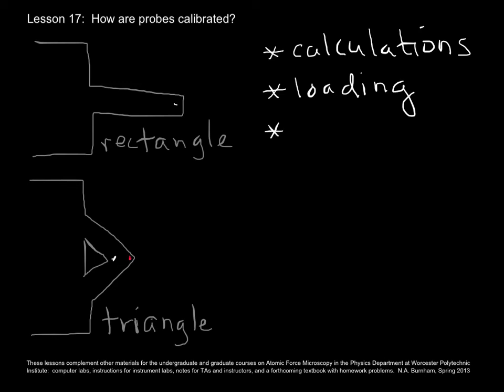There are a variety of options that I would call geometric, which is you measure the width and length of your cantilever, and that you can do optically because the lengths certainly are big enough and the widths are generally big enough that you can see that in a calibrated optical microscope. And then you measure the resonant frequency and then calculate the spring constant.